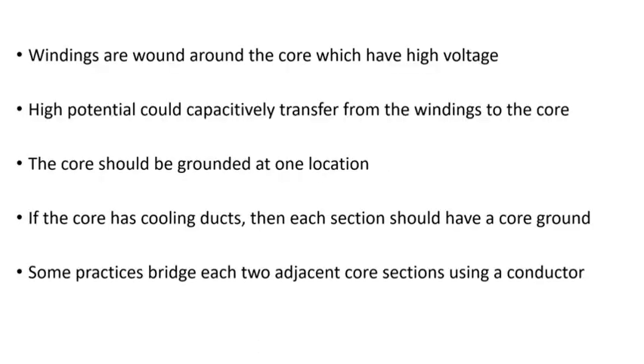In this video, I'll talk a little bit about transformer core ground. We know in a transformer the windings are wound around the core, which have high voltage, and because it's high voltage, whether it's a primary or secondary winding, high potential could capacitively transfer from the windings to the core, because we know there is insulation between the windings and the core, so the only thing really connecting the two is capacitance, because capacitance will always exist, whether you have a conductor or two conductors. So the core should be grounded at one location.